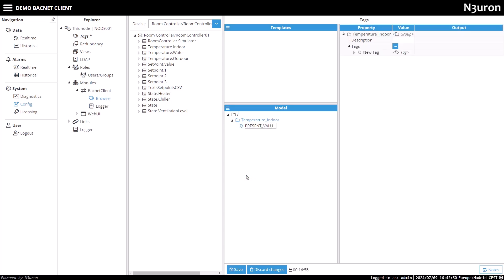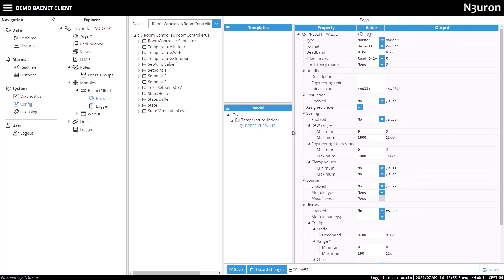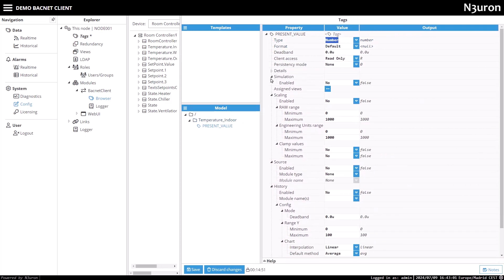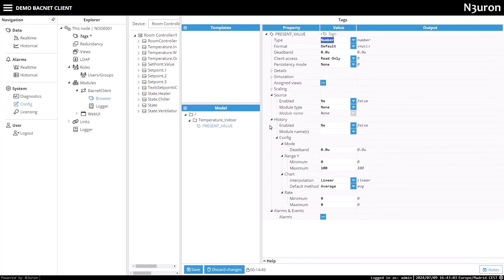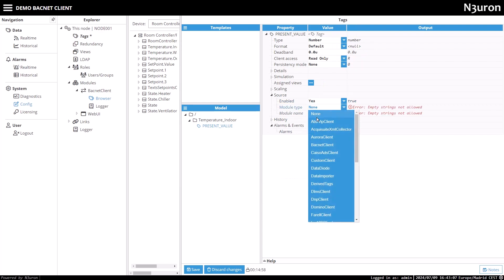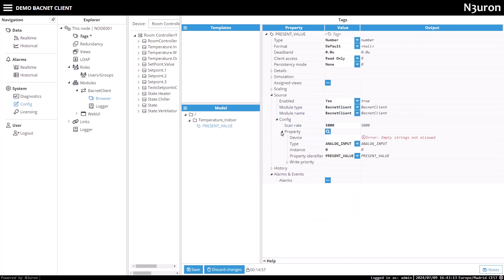Let's set the present value tag to the number type. In the source configuration, I'll enable the source and choose BACnet client as the module type from the drop-down menu. Additionally, remember to select BACnet client as the module name, as we named it earlier.